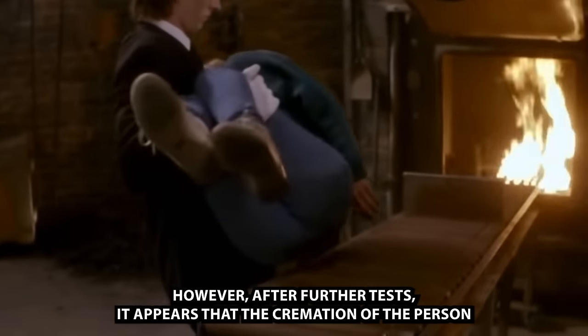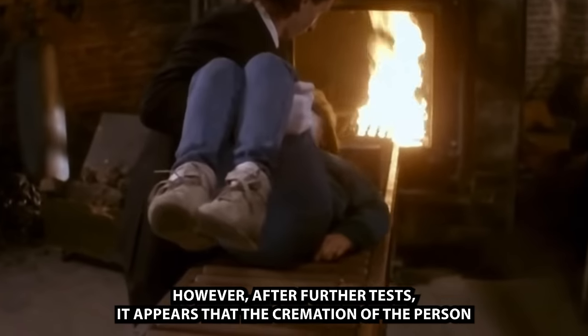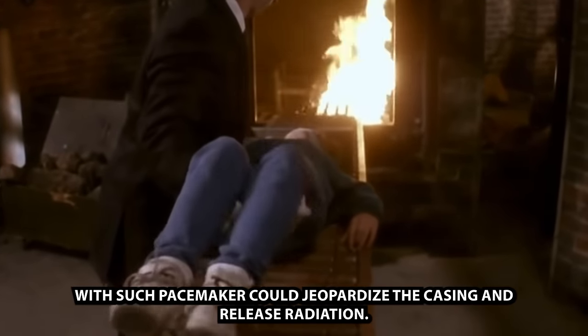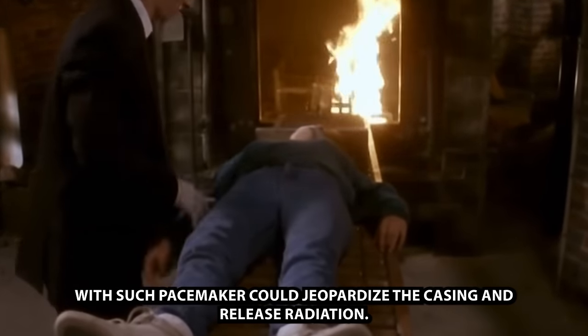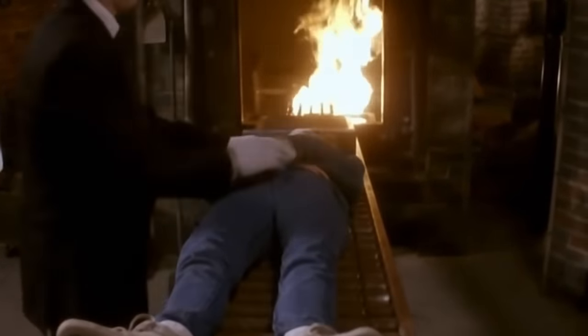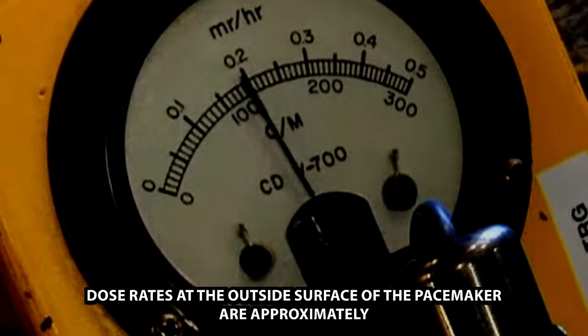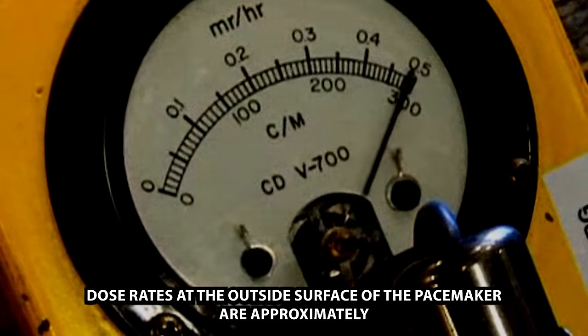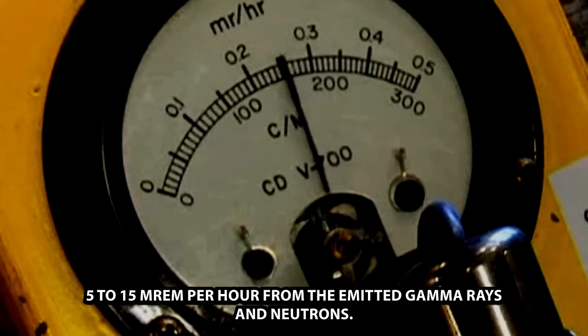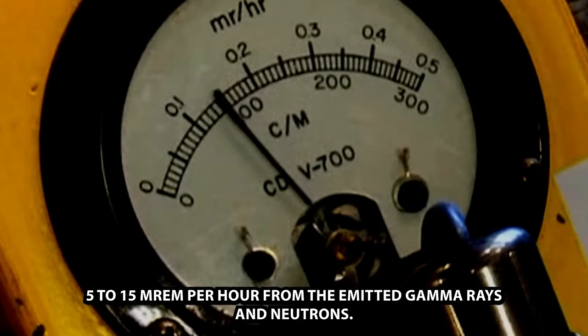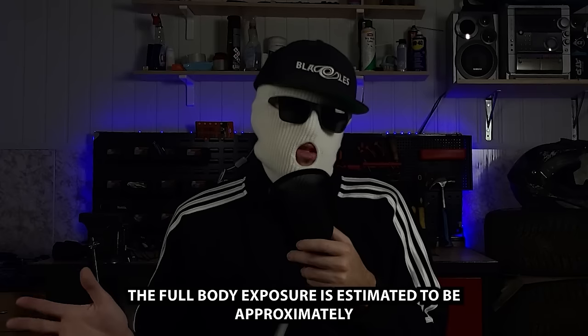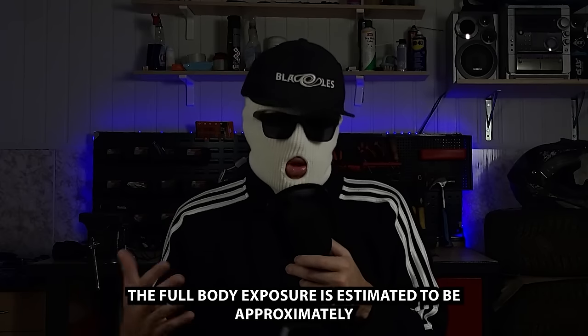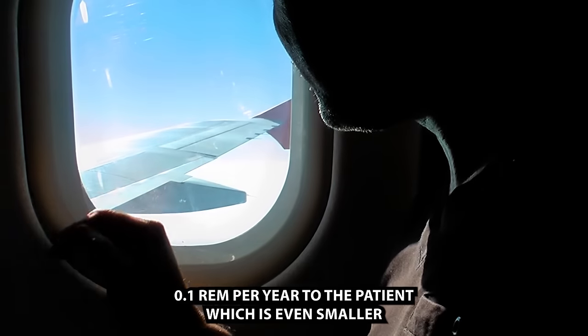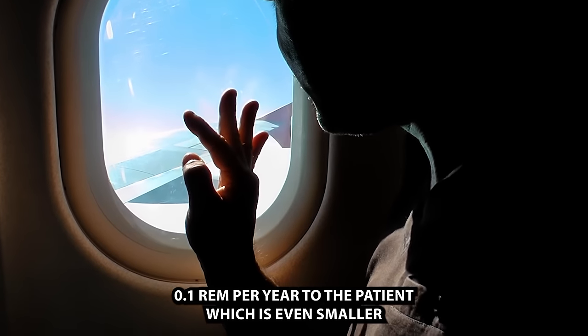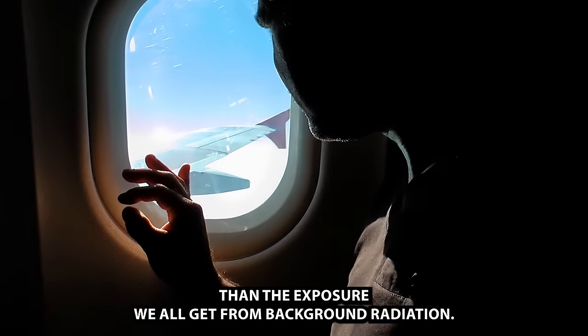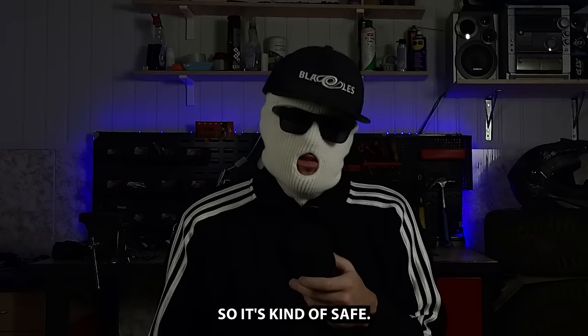However, after further tests, it appeared that cremation of a person with such a pacemaker could jeopardize the casing and release radiation. Radiation rates at the outside surface of the pacemaker are approximately 5 to 15 millirem per hour from emitted gamma rays and neutrons. The whole-body exposure is estimated at approximately 0.1 rem per year to the patient, which is even smaller than the exposure we all get from background radiation, so it's kind of safe.